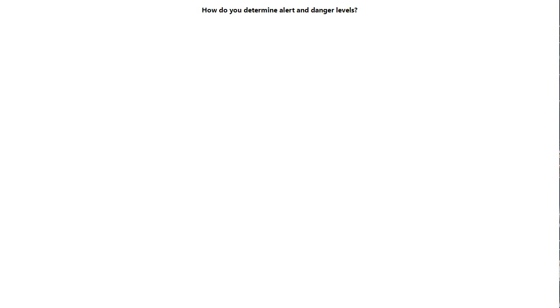Sure. This might tie into the previous question too. As you know, we typically defer to the OEMs and their recommendations for stress levels, so if you have a machine we'd recommend consulting with the OEM. In the absence of OEM guidance, we follow basic stress cycle calculations and counting using Miner's rule. If we know the shaft material, we can step you through what that approach gives for alarm settings on the rain flow counter, the stress cycle counting. For amplitude levels on the spectral bands, we look at specific spectral frequencies and how those relate to the inferred stress on the shaft, making sure you're staying in the infinite life region of the shaft.